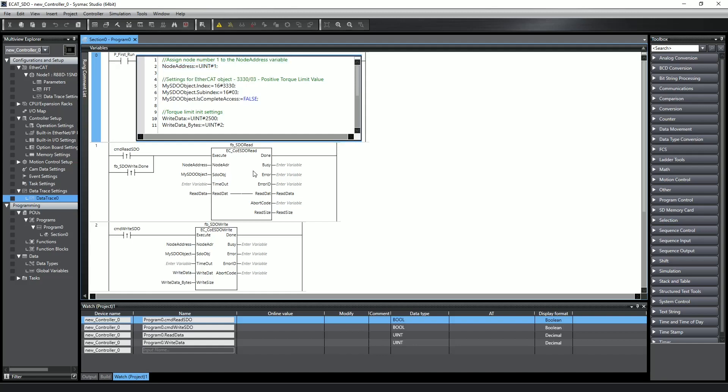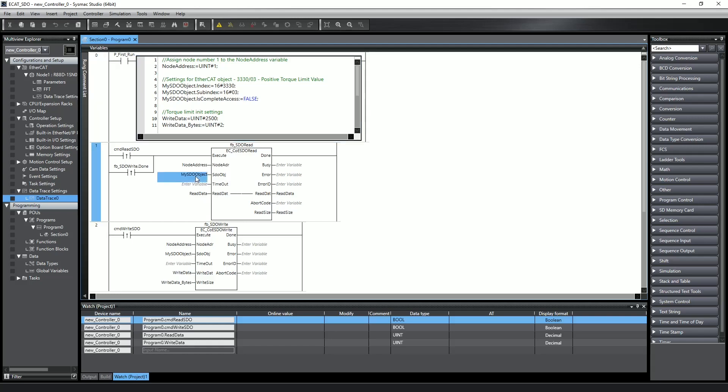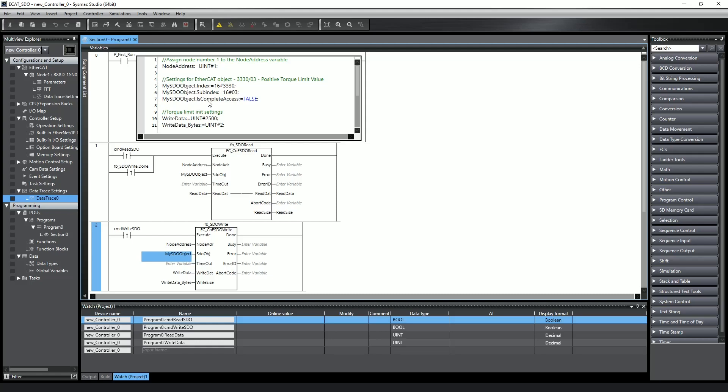The SDO object variable is a data structure of type _sSDO_access, which I called mySDO_object and used for both the read and write function blocks. The data structure has three elements: an index number, a sub-index number, and a boolean element if you want to access all sub-indexes underneath that index.